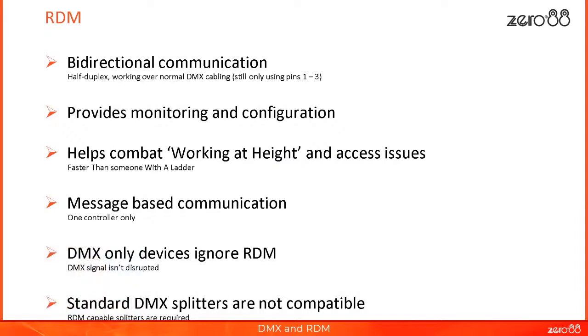Standard DMX splitters are not compatible with RDM — you cannot send RDM messages through a DMX splitter successfully. You need an RDM splitter. The Splitter 8 I showed you is an RDM splitter; there are plenty of others on the market, a bit more expensive but not dramatically so. Just be aware that you need RDM-capable splitters if you want to use RDM.